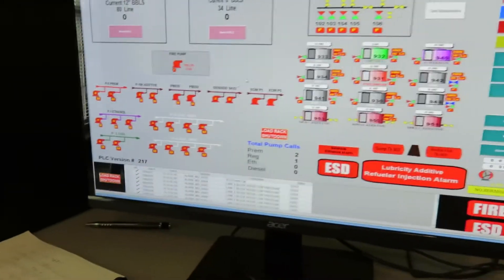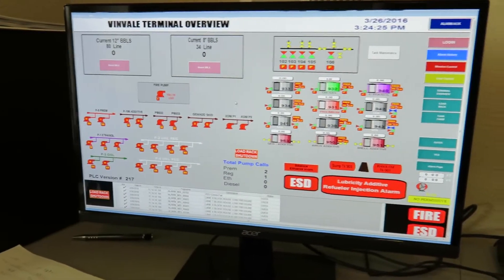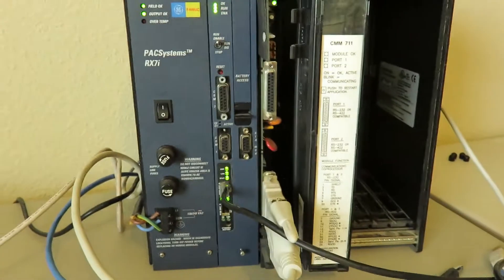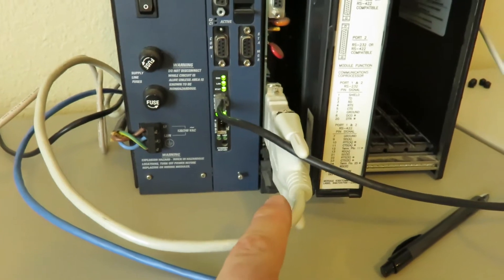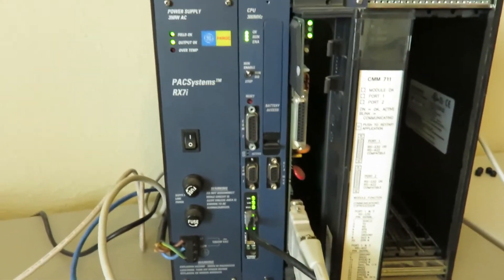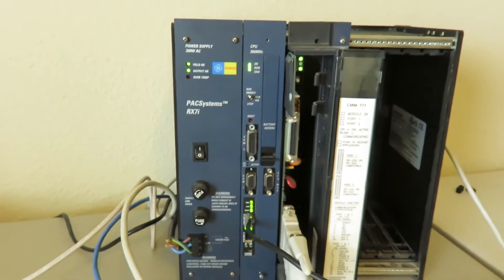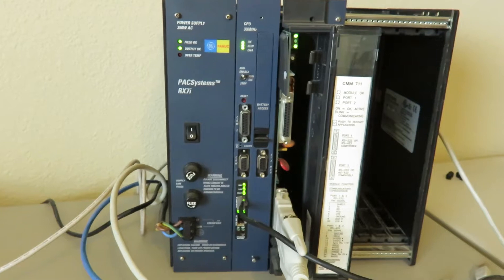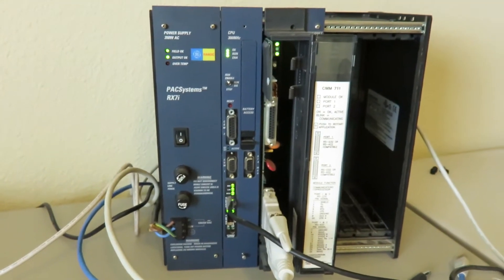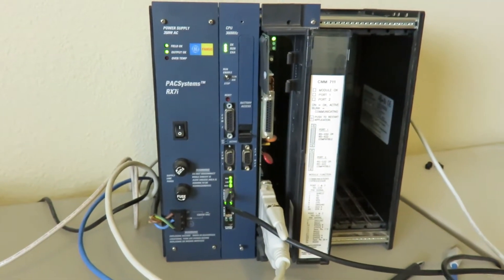And we're running the SCADA system that's communicating to the HMI through this serial connection which is a 232 connection. This happens to be running the Modbus protocol. 19, 2, odd, none, and 1. It's the comm settings.